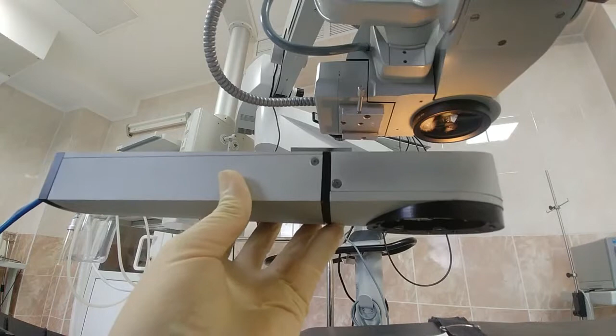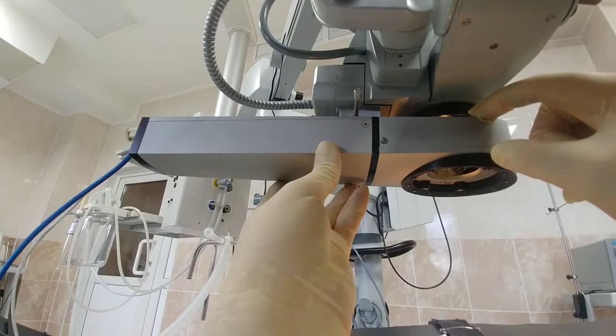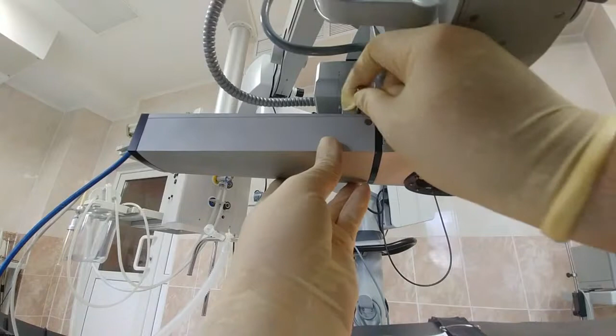The next step is mounting the keratoscope on the microscope. We insert the top dovetail into the dovetail adapter on the microscope and tighten the screw. The position should be controlled by the position of the objective. There is a round aperture at the top of the keratoscope that needs to be roughly aligned with the objective center. Then you tighten the holding screw. Place some kind of target underneath the microscope and make sure that the microscope view is unobstructed.